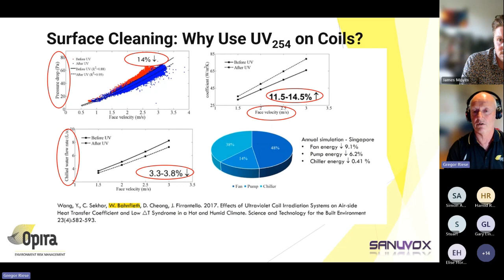In more temperate regions, it's not as statistically significant, so no one's claiming it's fabulous. But for example, if your building is Well accredited - one of the holistic building quality standards - and you have UV in front of the coil, you don't have to do a quarterly clean of the coil. So building owners that are Well accredited often flick to UV on coil for that reason, wherever they happen to be.